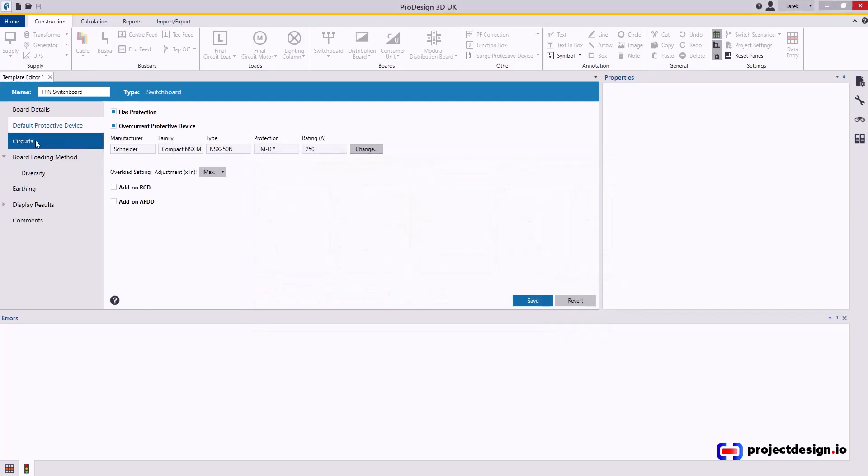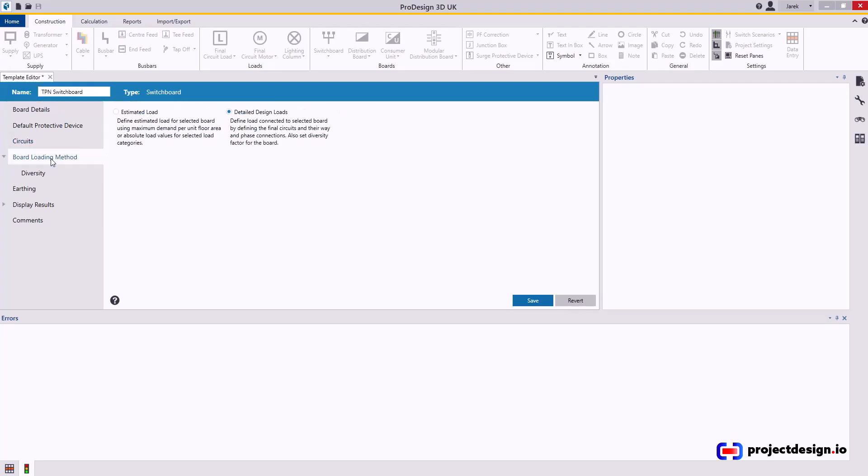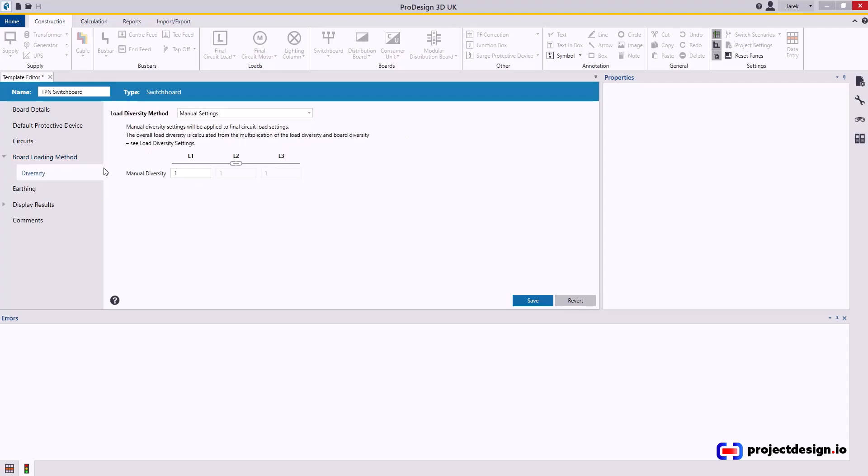Now go to Circuits. No point to put in the circuits, but loading method, always leave it as design loads. Diversity I will leave at 1, although it's very common to diversify the main switchboard to 0.9, so you may as well put it now, but my preference is to leave it as 1.